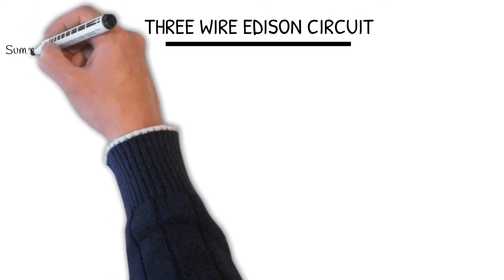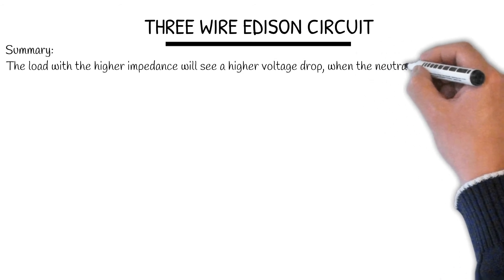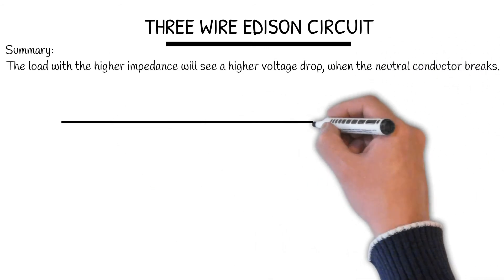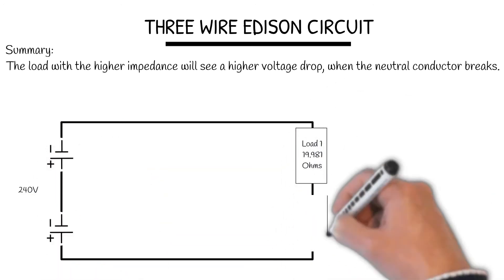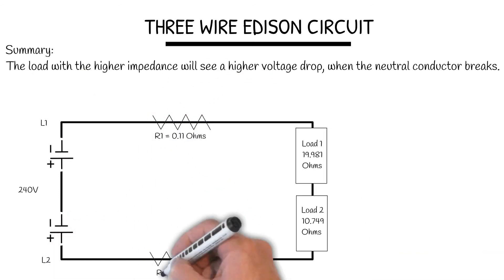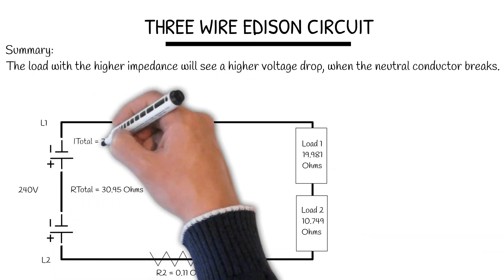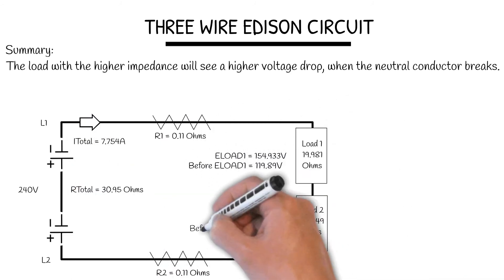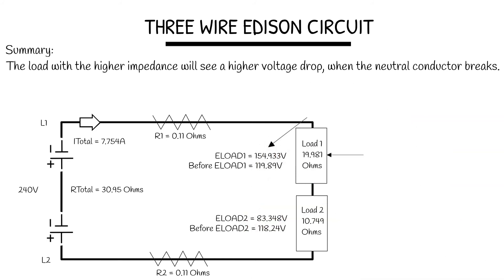3 Wire Edison Circuit summary. The load with the higher impedance will see a higher volt drop when the neutral conductor breaks. As you can see, Load 1 has 19.98 ohms, which is higher, therefore it has a higher volt drop.